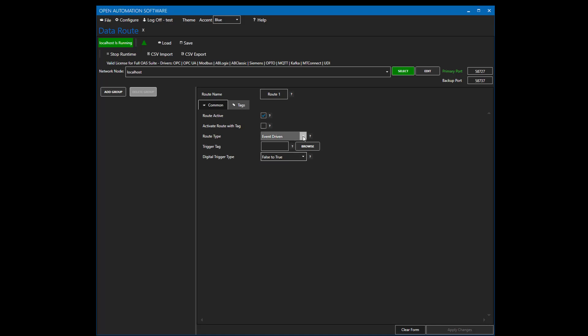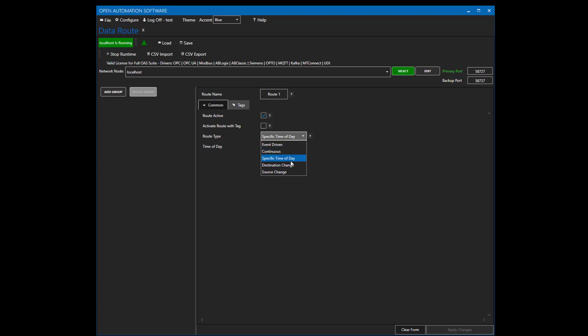If the route type is continuous, you specify the rate at which you want to execute the route. We can also do a specific time of day. With destination change as the route type, if the destination tag value changes, the route executes for just that destination tag. With source change, the route triggers a write to the destination tag any time the source tag defined to that destination tag changes. Let's change the route type back to event driven.